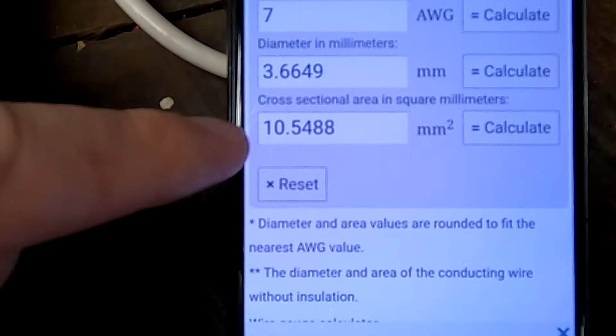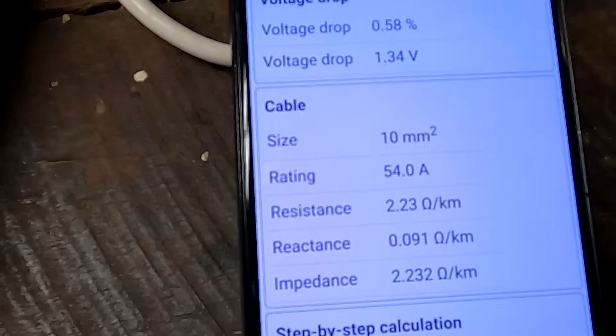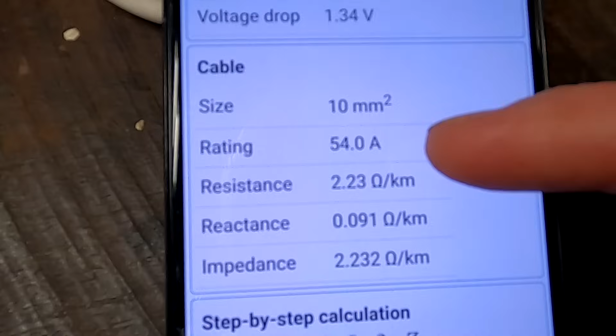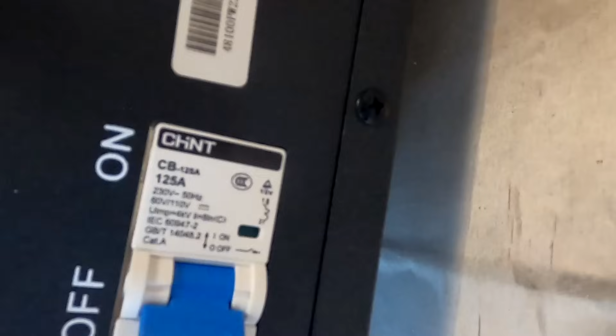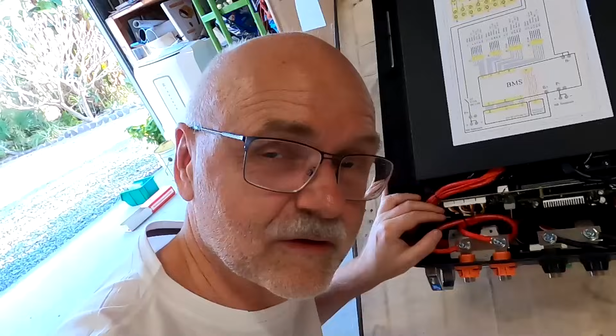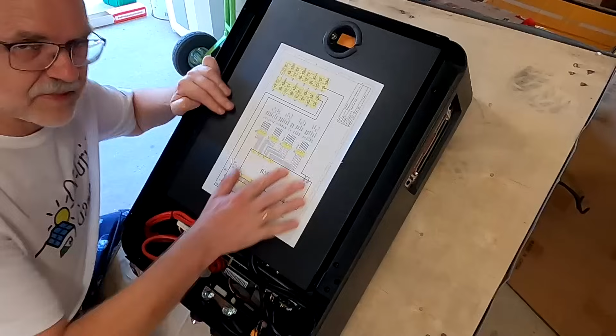The 7-gauge wire is around 10.5 square millimeters, and 10 square millimeters is able to carry around 54 amps. Times 2 makes 108, and we have a 125 amp circuit breaker here. These are super fine stranded silicone cables and can carry a lot more current than normal cables. From a pure cabling and safety perspective, thumbs up.